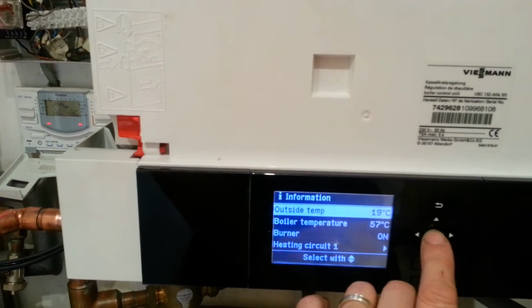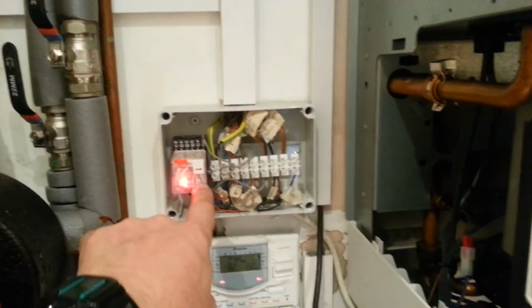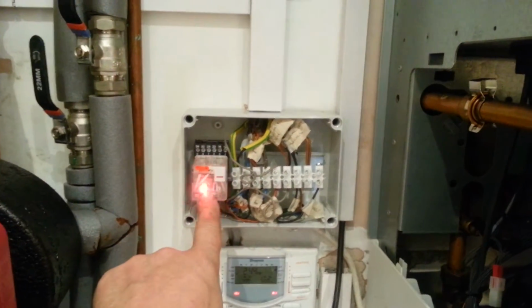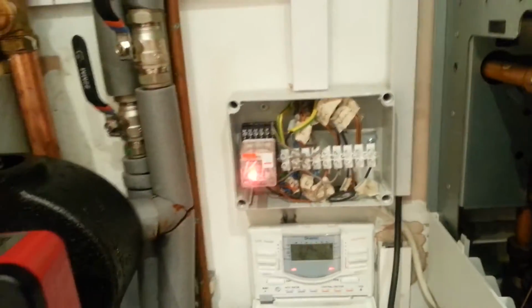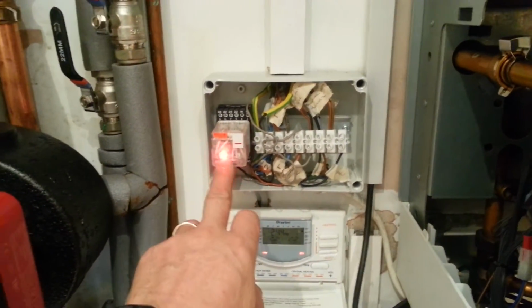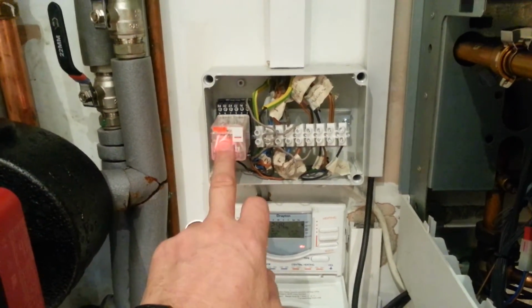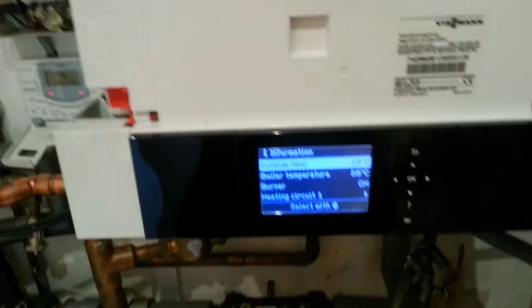We go into information here. At the moment we're in hot water mode, so we've got to see the light on the relay that I've wired in here. This is using a relay box off of Vitodens 100, which is in the back of the boiler here somewhere, so that when the stats on the cylinders operate, they're not really Viessmann compatible. They trip a relay which actually operates the Viessmann 100 relay in the back there, and that will give a false reading to the boiler.